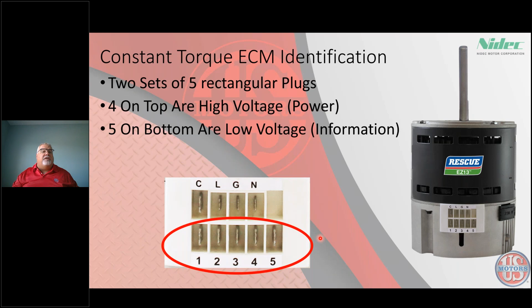It comes pre-programmed out of the box. This is your pre-programmed levels. Tap 1 is your low at 40% of full speed, and tap 5 is 100% of full speed. So there's options and variations of how you can wire this motor to get the different speeds that you require. And we'll talk about that when I talk about programming and why that's important and why we want to make sure we measure airflow even after we just drop this motor in and replace it, because it will have a significant effect on how that motor operates. We have 3 models now, a half to a third, a 3/4, and a 1. You'll see those model numbers there.